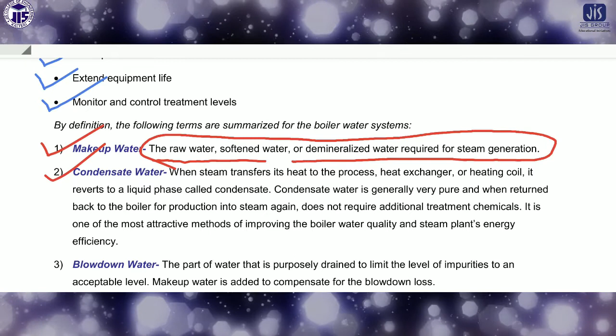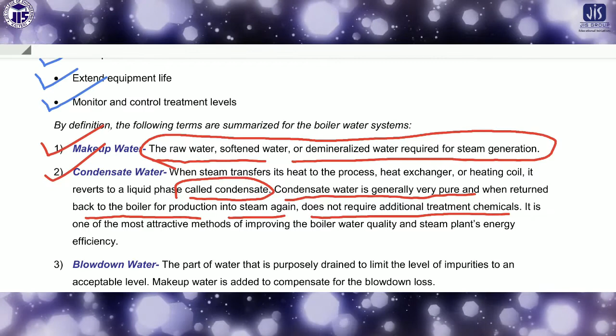Now condensate water. That means when steam transfers its heat to the process heat exchanger or heating coil, it reverts to a liquid phase called condensate. So condensation occurs again. Condensate water is generally very pure, and when returned to the boiler for production into steam, it does not require additional chemical treatment, because after heating it cools down, then again comes to the boiler chamber. That's why further treatment is not required, because in this process we purify the water. It is automatically purified, so no further purification is required. It is one of the most attractive methods of improving boiler water quality and steam plant energy efficiency. It is the most important way.